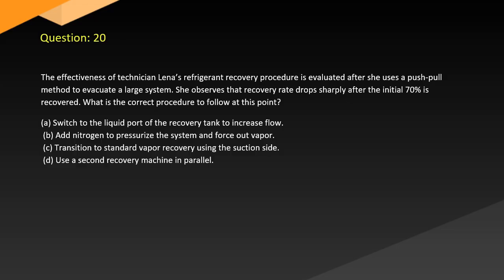Question 20. The effectiveness of technician Lena's refrigerant recovery procedure is evaluated after she uses the push-pull method to evacuate a large system. She observes that the recovery rate drops sharply after the initial 70% is recovered. What is the correct procedure to follow at this point? A. Switch to the liquid port of the recovery tank to increase flow. B. Add nitrogen to pressurize the system and force out vapor. C. Transition to standard vapor recovery using the suction side. D. Use a second recovery machine in parallel.